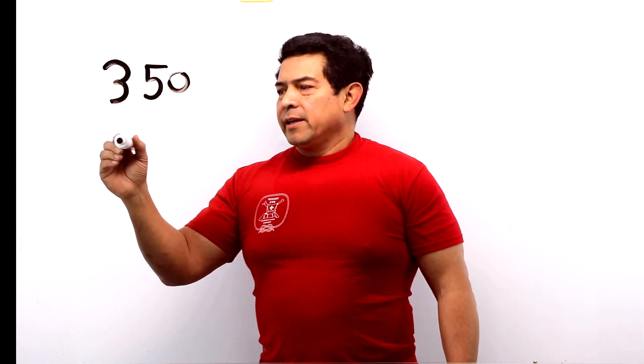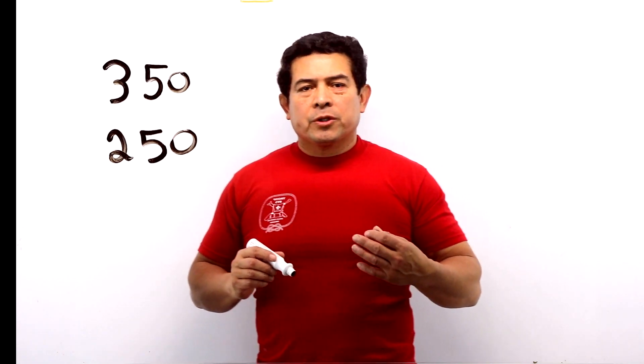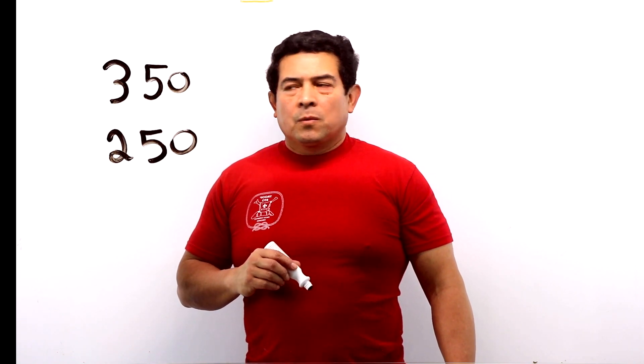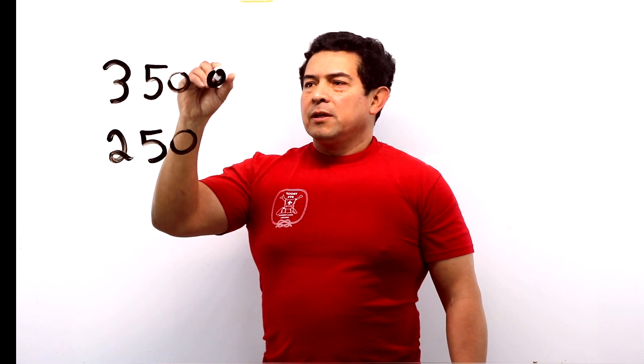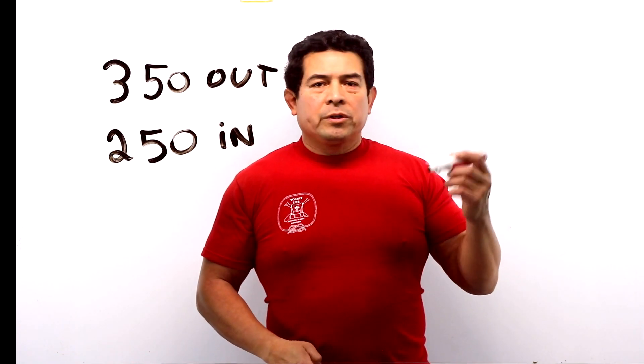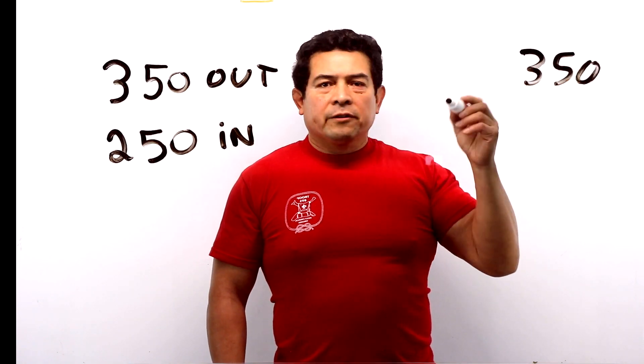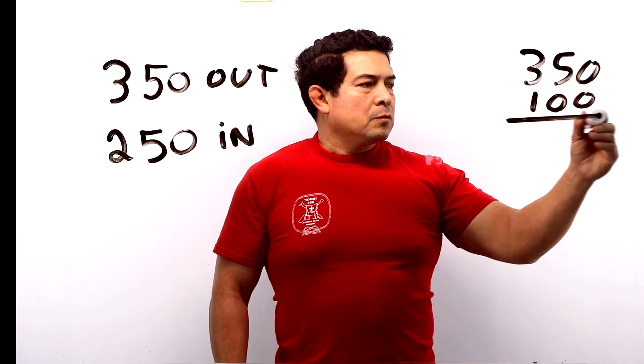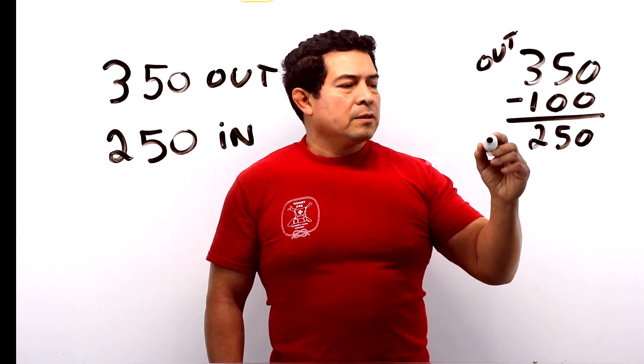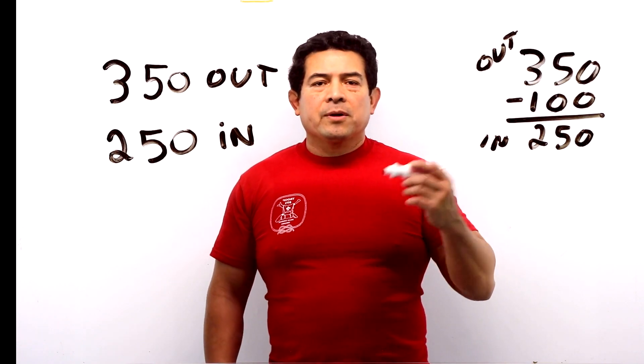We want it to come back in at 250 PSIG. So now when you buy a high pressure switch, usually there's going to be a little phrase on there that says cut in is cut out minus the differential. If 350 is going to be the cut out and 250 is going to be the cut in, we set the cut out at 350 and the differential we want to be 100. When we subtract, we end up with 250 PSIG. So it's going to cut out at 350 and it's going to cut in at 250. That's what they mean when they say cut in is cut out minus the differential.